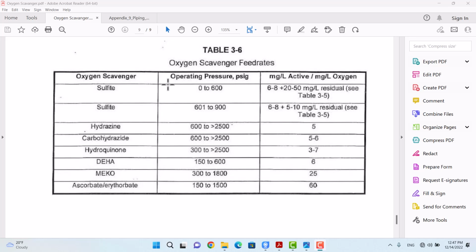each of these chemicals, for about 1 or 2 months, and test them, and fill in some information about their consumption and their performance on the log sheet. At the end of the field test, the best manufacturer, the best product in terms of consumption and performance, is selected. I've done this for all of my chemicals in my plants.